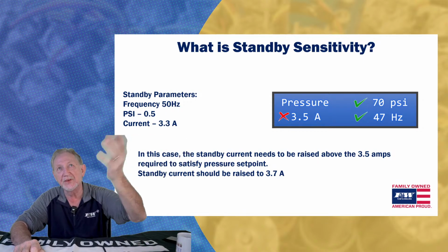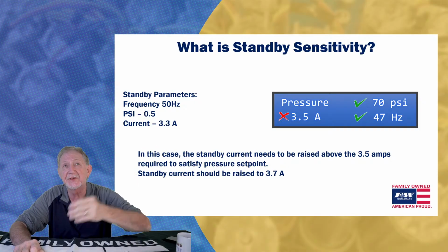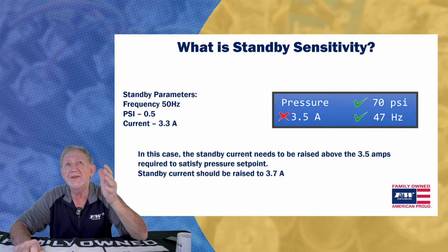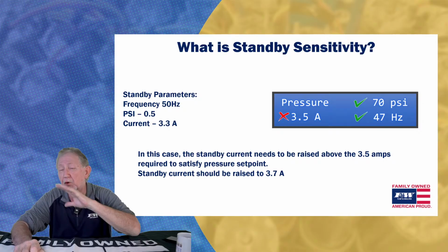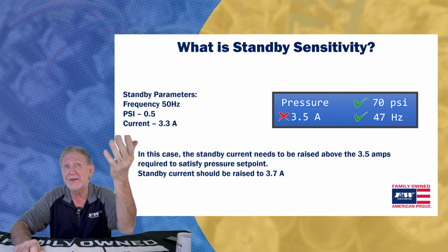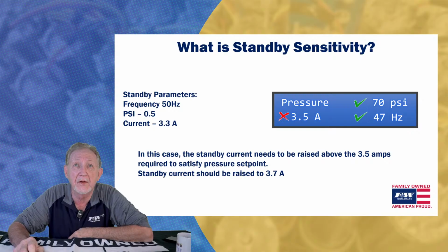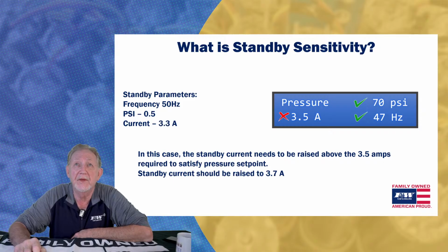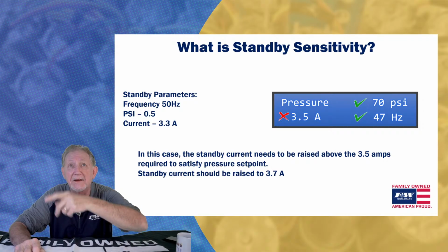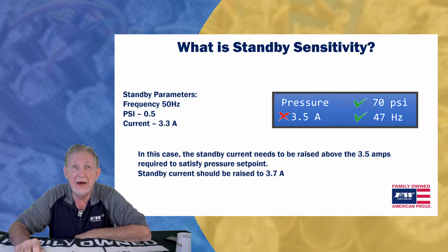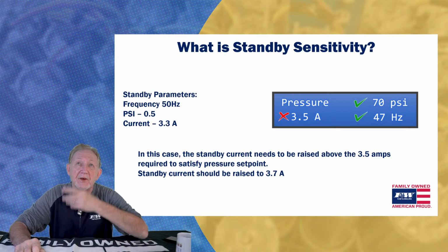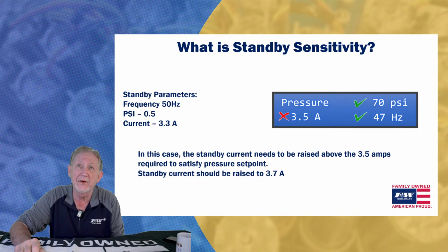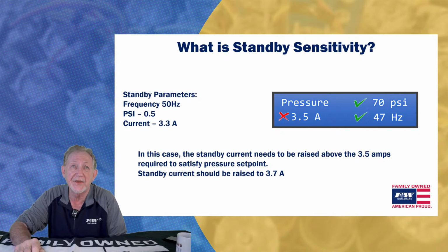And so therefore, the drive thinks water's still being used somewhere. So that's perhaps a nuisance fault that we can address here, because if you replace this drive with another like drive, this same problem could occur. The way that we address it is very simple. We're going to go into that set point for that 3.3 amps. We're running at 3.5. So we need to get that set point above 3.5 so that we get a green check mark on all three of those measurables, and the thing goes into standby.